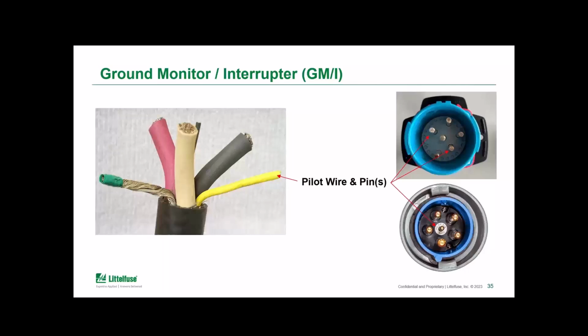Now that we have really gone through and hashed some of the ground monitoring functionality, I just want to show one other aspect of the application. So I mentioned before that the pilot or the ground check conductor is typically used to perform this ground monitoring. On the photo here, just showing one example of a cable on the left that has that additional pilot wire included. And couplers are also available that have the pilot pins included in them.